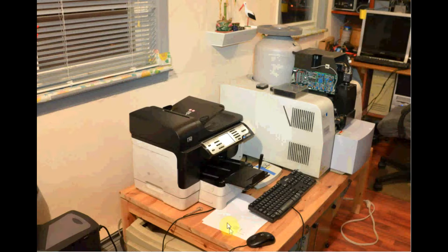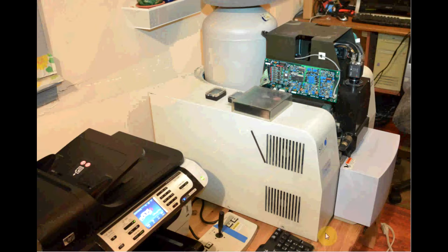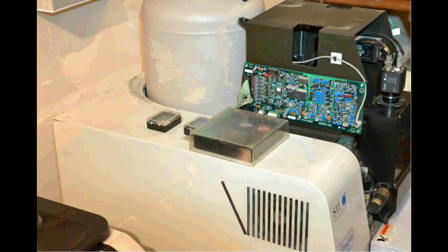There is a drawer that is open up. Here we have a camera and part of the electronics, and the printer that is printing out the report automatically when enabled, and the screen is not being seen here. Let's go further. Here we have a closeup of the nitrogen tank, and the camera is in here. That's the drawer. Let's go further. That will be the calibration fixture and two plates with known parameters, so it could be used also to check out the accuracy. This is the nitrogen tank, camera shown, the high voltage power supply, and there we have the screen, and this is the key for the X-ray tube, and this is the main switch.